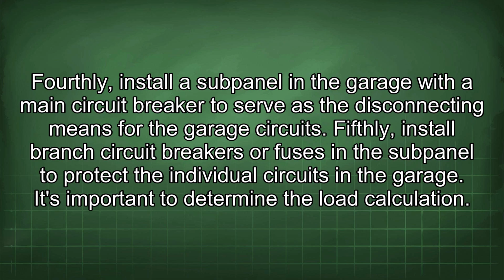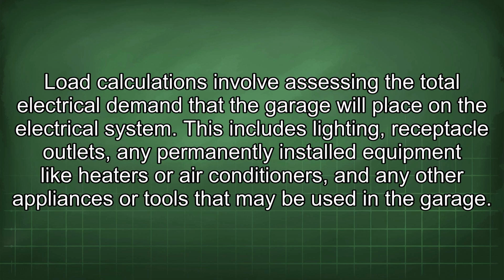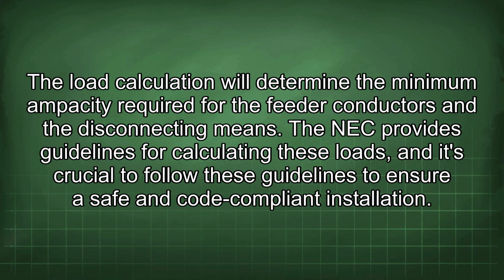It's important to determine the load calculation. Load calculations involve assessing the total electrical demand that the garage will place on the electrical system. This includes lighting, receptacle outlets, any permanently installed equipment like heaters or air conditioners, and any other appliances or tools that may be used in the garage. The load calculation will determine the minimum ampacity required for the feeder conductors and the disconnecting means. The NEC provides guidelines for calculating these loads, and it's crucial to follow these guidelines to ensure a safe and code-compliant installation.